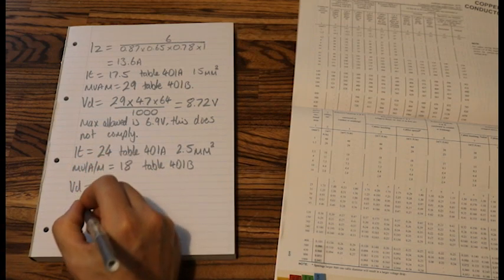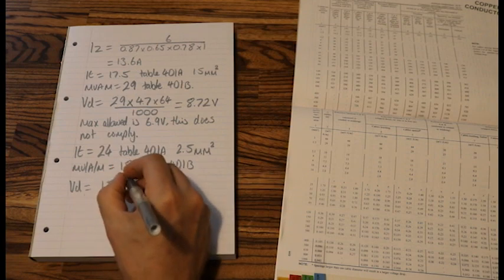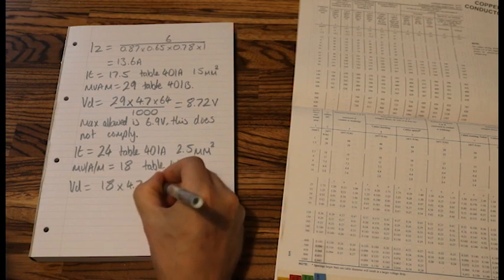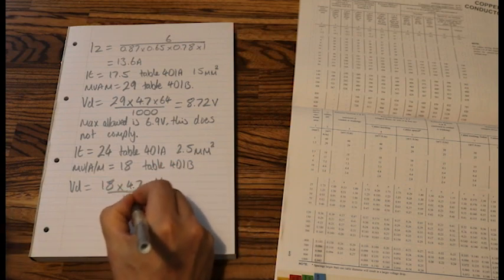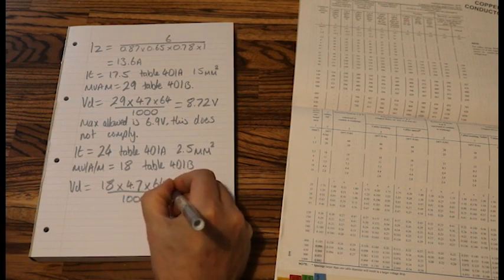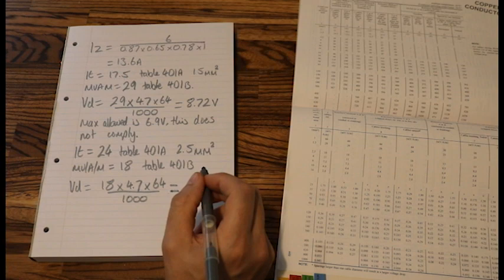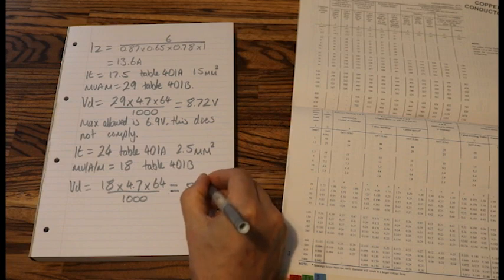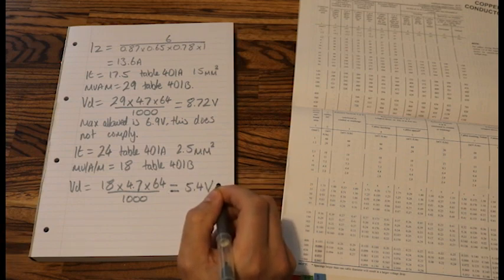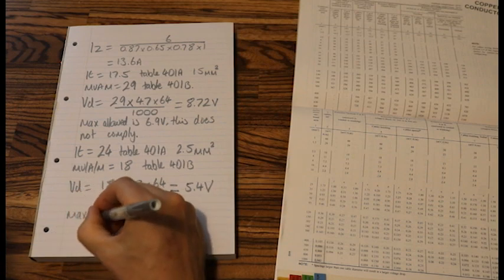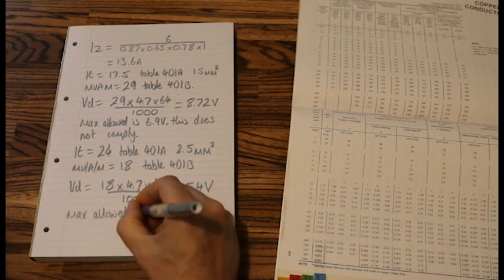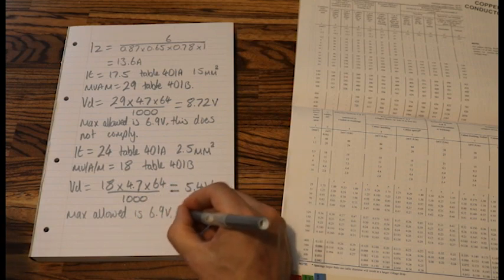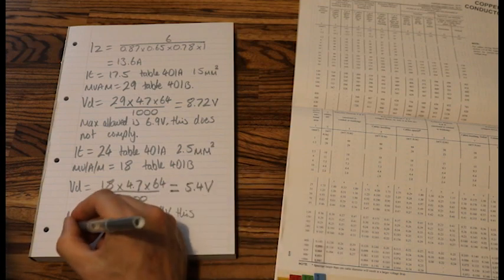And now we do our Voltdrop formula once again. So our Voltdrop formula now becomes 18 times my IB, 4.7, times my length, 64, divide 1000, and that should equal 5.4 volts. Brilliant. Now we can write, max allowed is 6.9 volts. This complies.